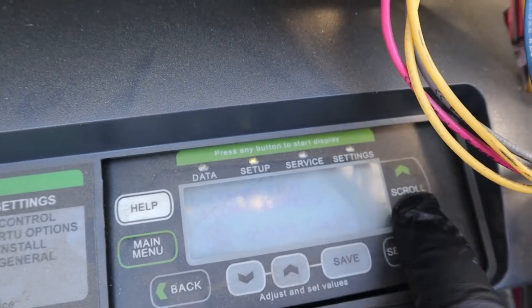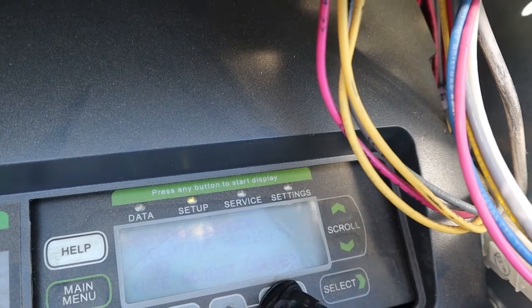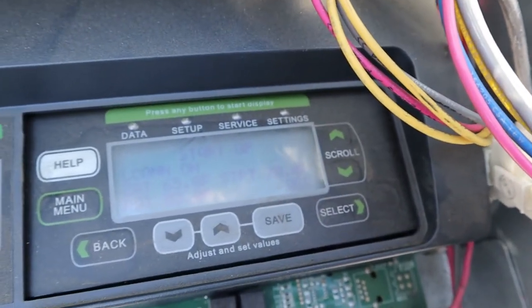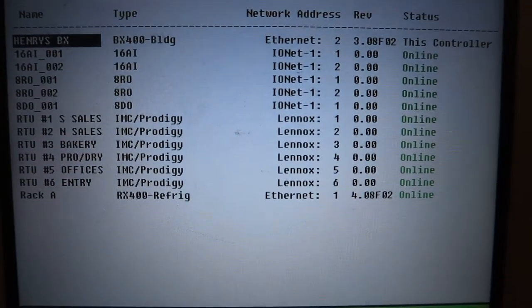This would be number six — let's see what this one is set up as. Number six is actually set up as number two. So I've got two units addressed as number two — that's where my conflict is. I have a sensor going straight to the Lennox Prodigy, not going off the E2. The Prodigy tells the E2 what temperature it is, and the E2 gives the set points back to the Prodigy.